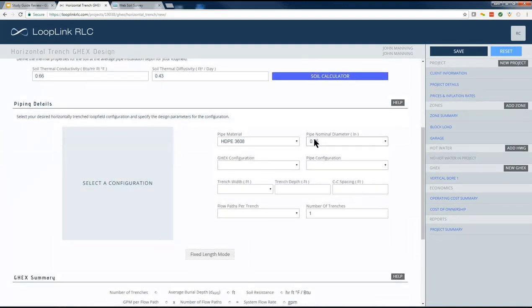So with your soil properties identified, the next thing that you need to do is specify, again, ground heat exchanger material, loop size. For the most part, you generally want to stick with a 1 loop per ton layout with horizontal trenched. And what that means is you want to stick with 3/4 inch loops and a 1 loop per ton layout. Because those larger pipe sizes can become difficult to wrestle with, especially if you're trying to bend them into a slinky shape or whatever it happens to be. So I'm going to stay with the 3/4 inch loop.